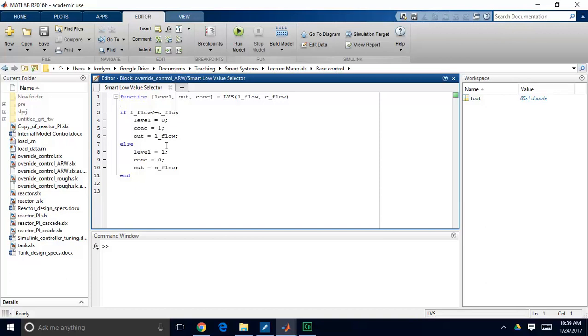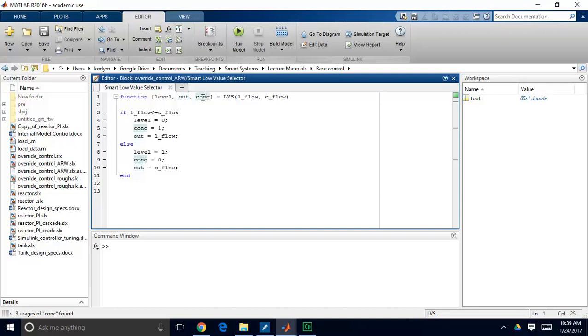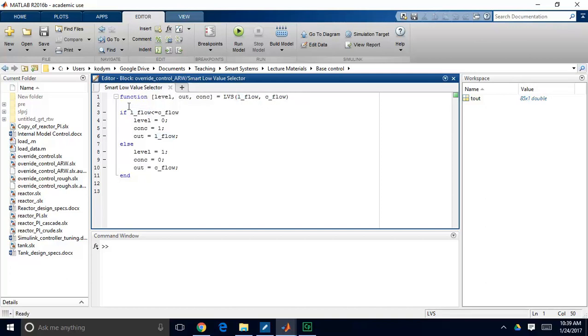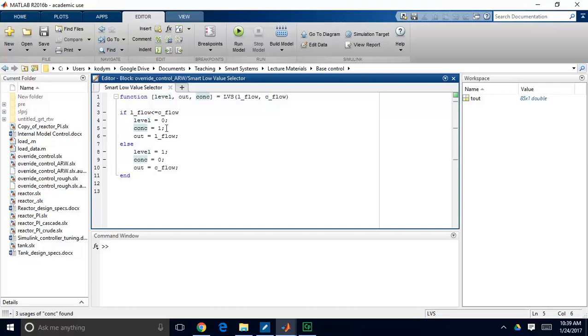So let me walk you through this function. So my outputs to the function are this variable called level, which is an indication of whether you're in level control or not. This out, which is just picking the lower of the two flow control signals. And this conc variable, which is telling me when my concentration controller is in control or when it's not. My inputs are just my level flow control signal and my concentration flow control signal. So I just have a simple if statement. So if it should be in level control, meaning my level flow signal is lower than my concentration flow signal, I want to set this level variable equal to zero, and I want to set this concentration variable equal to one, and I want to pick this L underscore flow, my level flow control signal, to be what I actually send to my valve.